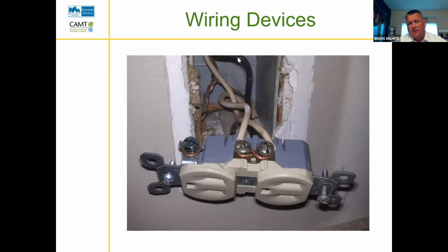Wiring devices. If we look here at our electrical outlet, what's wrong with this picture? Neutrals are touching? Does that matter? Not really. No, that doesn't matter. Anybody else see anything wrong here? I don't know if this is the correct answer, but whenever I tighten them around the screws, I make sure they face both the same way and face the way as you're tightening down, so they kind of set firmer in the screw. But that is the right answer.